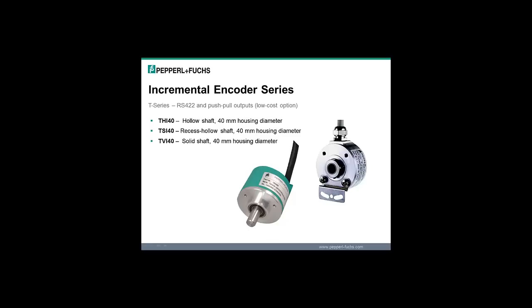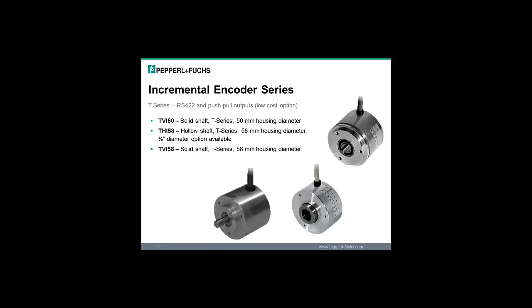The T-series encoders have 5 to 30 volts DC and is a lower cost option. Applications that need 1,024 pulses per revolution or lower should look first at the T-series. Different housing diameters and shaft options are available. In the T-series, the TVI-50 is a solid shaft, 50 millimeter housing diameter. The THI-58 is a hollow shaft, 58 millimeter housing diameter with a half inch diameter option available.